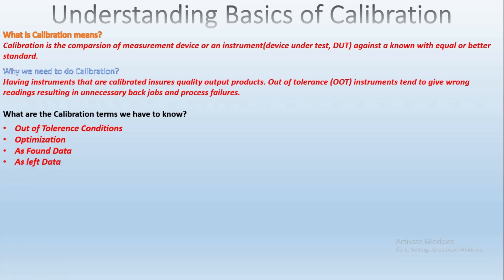The next term is as-found data — the reading of the instrument before it is adjusted is called as-found data. And as-left data is the reading of the instrument after adjustment, or the same as the as-found reading if no adjustment was made.